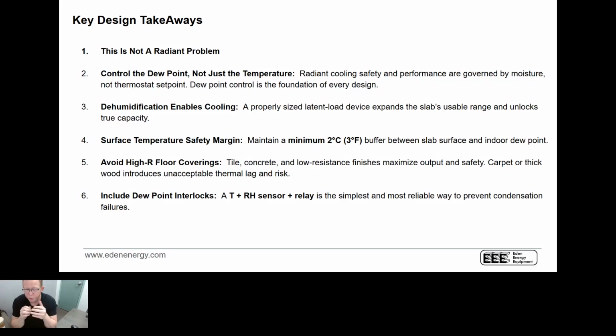We also have to be careful that if we're designing a system around tile, it's got a low resistance finish. If somebody goes in and puts thick carpet in, that's going to have a big, big impact where, yes, if we've done the right water temperature where it's not going to be a problem and we've got a humidity strategy control and a dew point control, it's not going to show up anywhere other than somebody's going to call you and say, I don't know what's going on. My air conditioning's been running all day. It's just not comfortable. And the answer is somebody went in after a designer that you didn't know about and said, we're going to put this really nice Berber carpet that's 2 inches thick. That's your problem. It adds a thermal lag and it can be a problem. So it's really important as we look at radiant cooling that we understand, unlike radiant heating, there's a lot of unintended consequences of assuming colder is better.